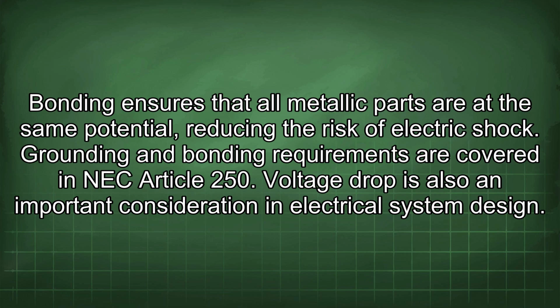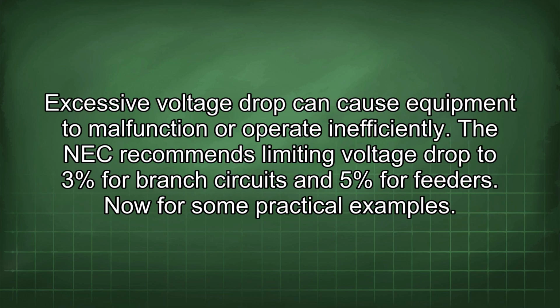Voltage drop is also an important consideration in electrical system design. Excessive voltage drop can cause equipment to malfunction or operate inefficiently. The NEC recommends limiting voltage drop to 3% for branch circuits and 5% for feeders. Now for some practical examples.